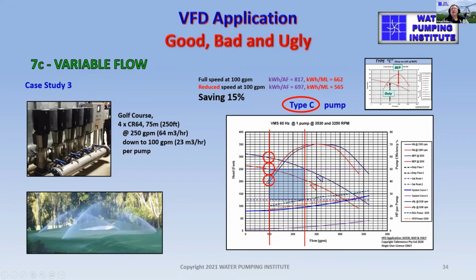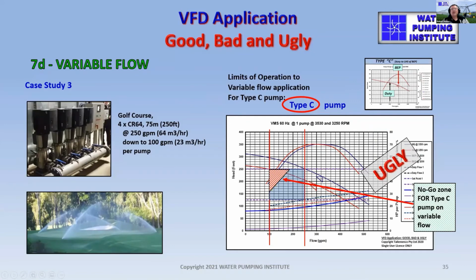And lastly, if we had a pump duty point operating to the left of BEP to start with, so here's BEP, and here's our duty point here. Full speed pump efficiency is 68%, and when we throttle it down, the pump efficiency goes down to 40%. That's particularly ugly. You would not want to do that. In fact, you could potentially be operating the pump in a harmful area. So with this particular application, we would like to have a no-go zone in this area of operation for a type C pump on variable flow.